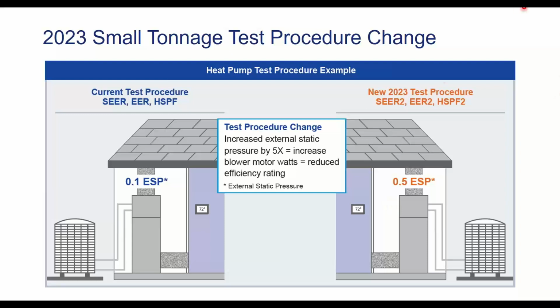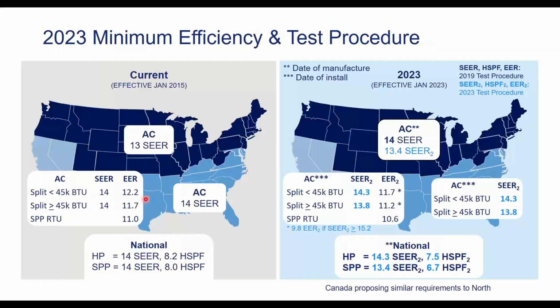So that new standard, to avoid confusion, there will still be confusion, but to try to avoid confusion, instead of SEER, it'll be called SEER2 or EER2 or HSPF2. So that 2 appendage on there means it's tested with the 0.5 inch external static pressure, and no 2 means it's the old obsolete standard with the 0.1 on there. So because of that, manufacturers are being required to change some of their equipment to become more efficient. So not only are we going from 13 to 14 SEER, but we're going to the new rating. So when all that gets kind of cobbled together, what we technically have to do is meet 13.4 SEER2. We don't have to actually meet 14 SEER, 13.4 SEER2. But 13.4 is not just 0.4 better than 13. It's a bigger leap because of the pressure. And the same thing with all these other ones.